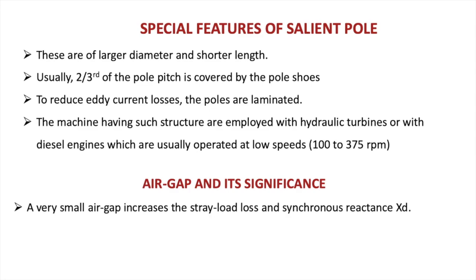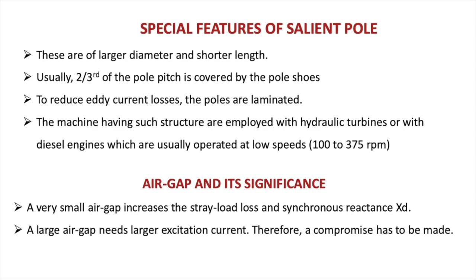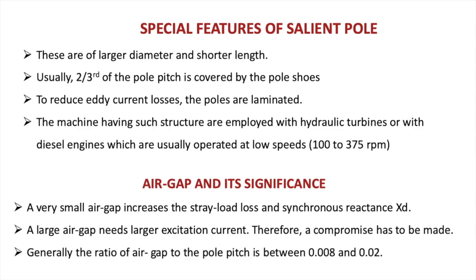There is an air gap between the stator and the rotor. So what is the significance of it? A very small air gap increases the stray load losses and the synchronous reactance Xd. A large air gap needs larger excitation currents. Therefore, a compromise has to be made between the gap length and the synchronous reactance. Generally, the ratio of air gap to the pole pitch is between 0.008 to 0.02.